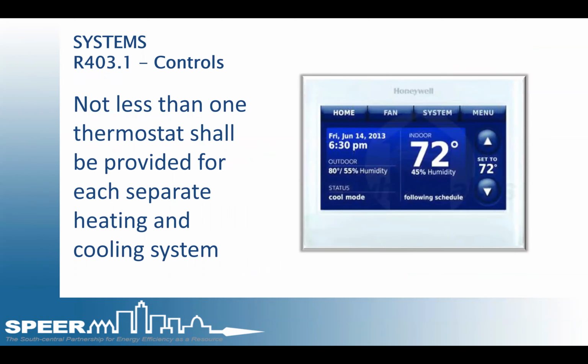Systems and specifically controls at R403.1: each HVAC system must have its own thermostat. Running more than one HVAC unit on a single controller is no longer allowed. Builders sometimes offer game rooms, bonus rooms, media rooms, additional bedrooms, and sometimes they just add that single extra bedroom or game room on top of a normally built single story. And if an additional HVAC unit is needed to cover the heating and cooling loads of those additions, it must be controlled by its own thermostat. It cannot be controlled by the main unit on the main floor.